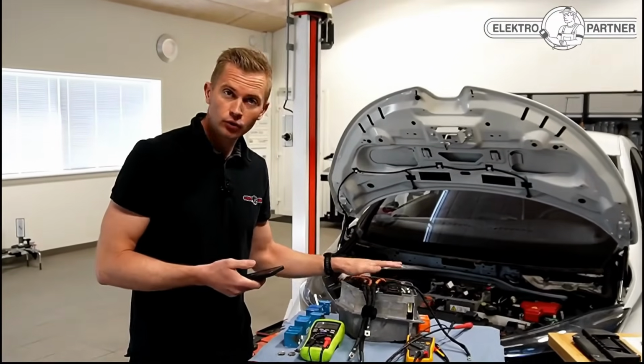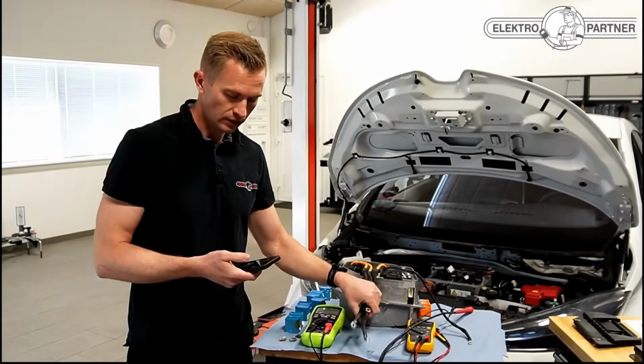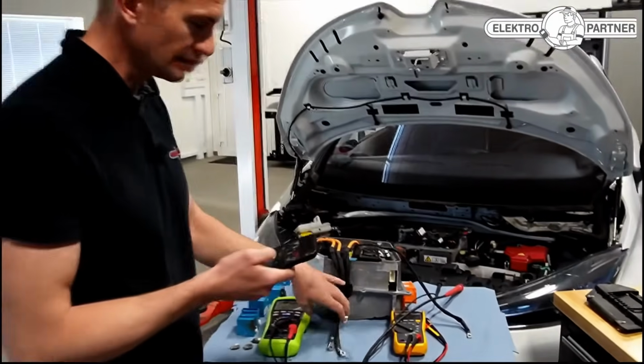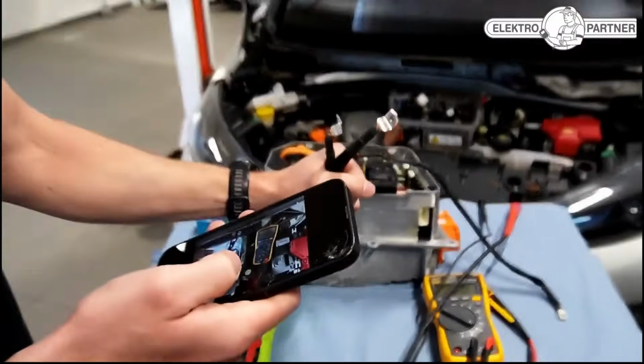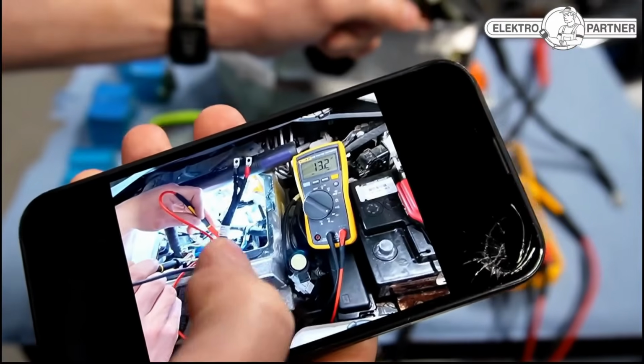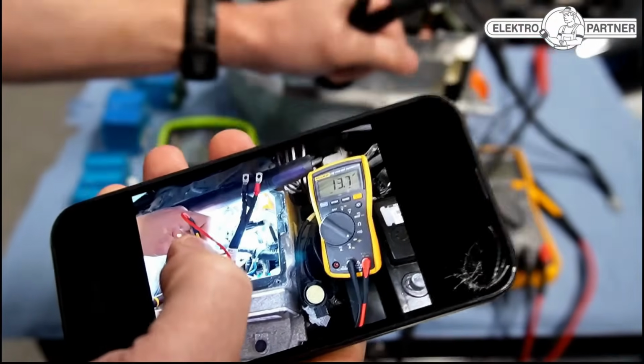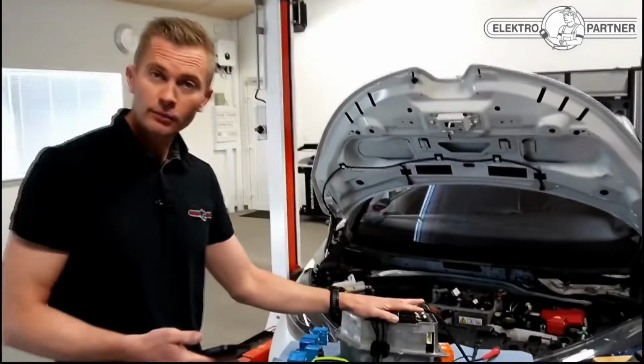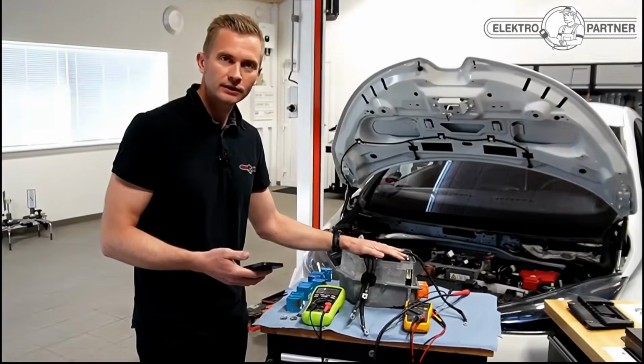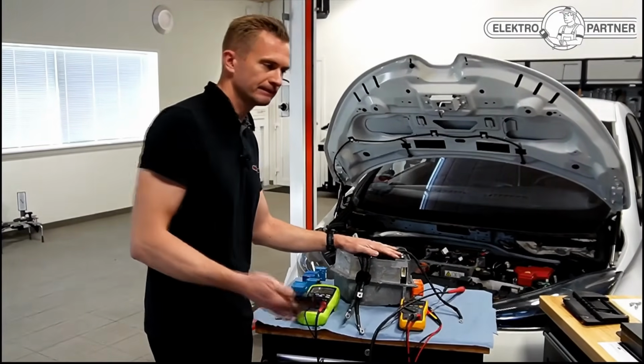Before we removed the filter, we took a few measurements across the phases, and we measured a capacitance between the phases of 18.3 microfarads, 13.2, and 13.7. It could be interesting to measure now, after we've replaced these capacitors, what we get when we measure across the same phases.